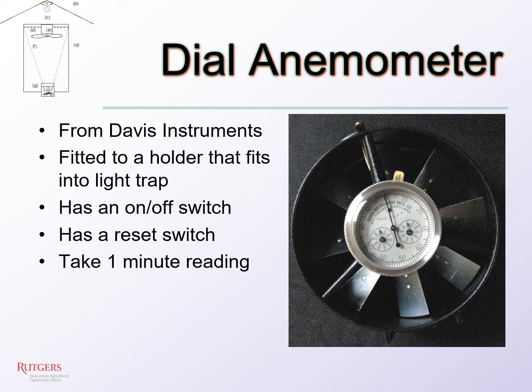This anemometer has an on-off switch at the side of the dial casing, as well as a reset switch just off from the face of the anemometer. To take a reading, make sure that the anemometer is set to 0. Count down using a stopwatch, turn on the anemometer, and let it run for 1 minute. At 60 seconds, turn off the anemometer and take a reading.